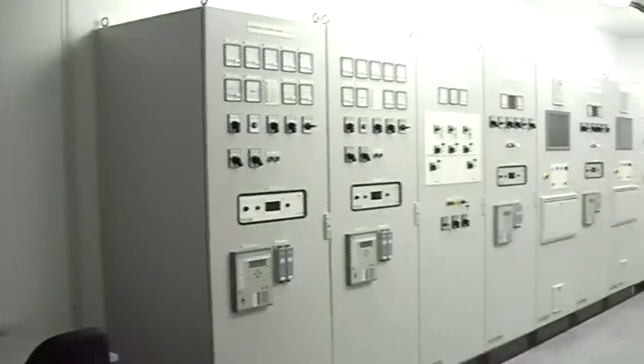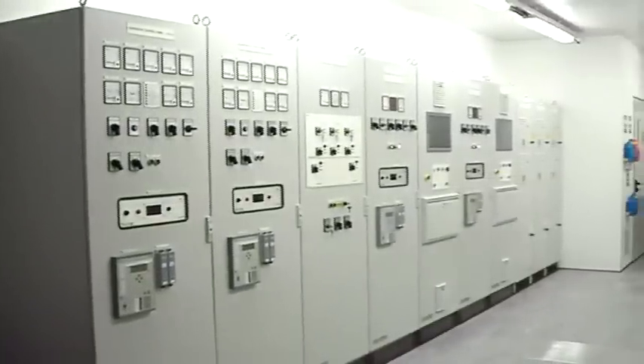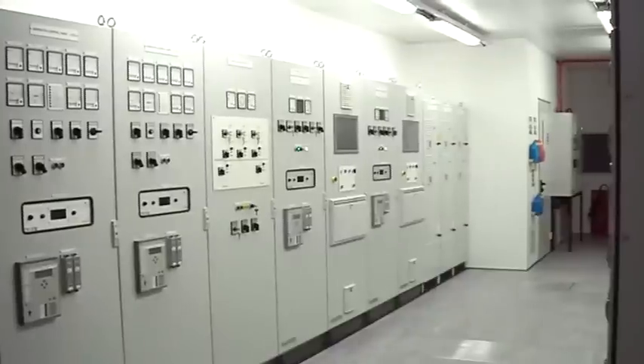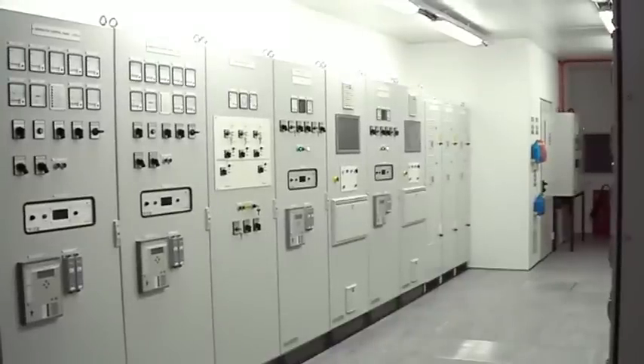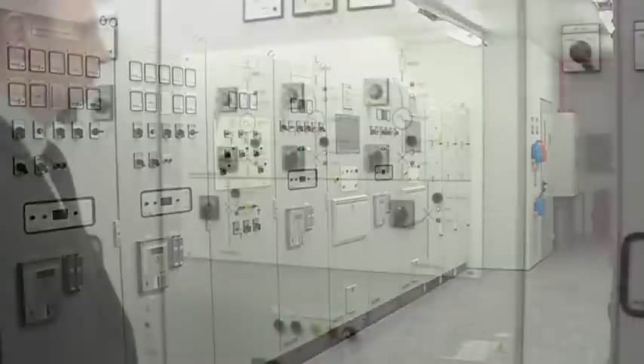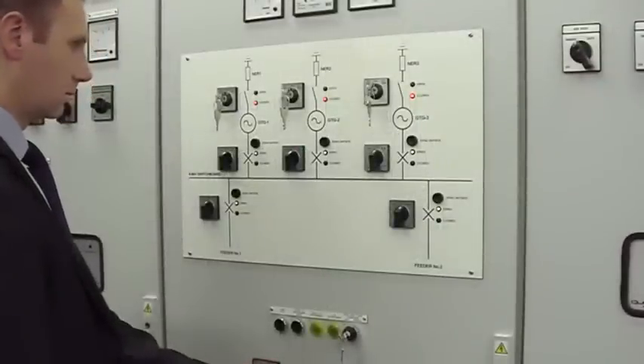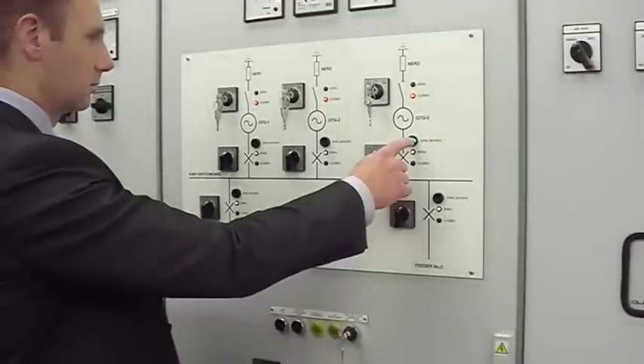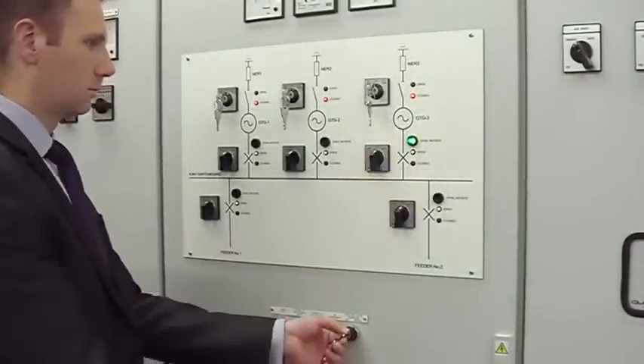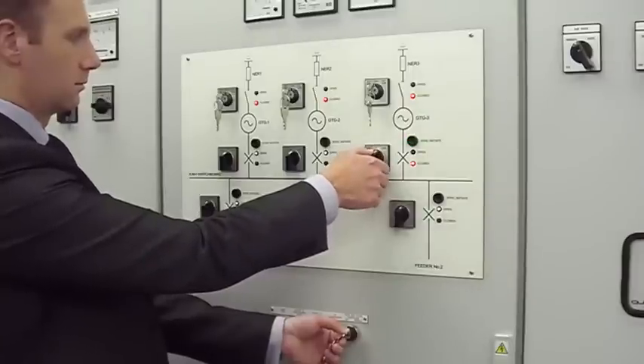The unit control panels and generator control panels are the brains of the power generation package. The unit control panel monitors vibration and controls the flow of fuel into the engine, whilst the generator control panel takes care of the electrical aspects, such as protection and controlling output voltage. A common synchronizing panel is used to synchronize the generators so that they can run in parallel with each other to provide the level of power required by the site load.